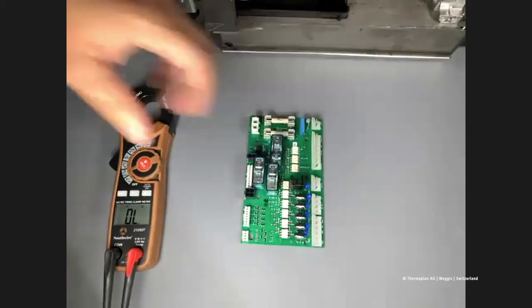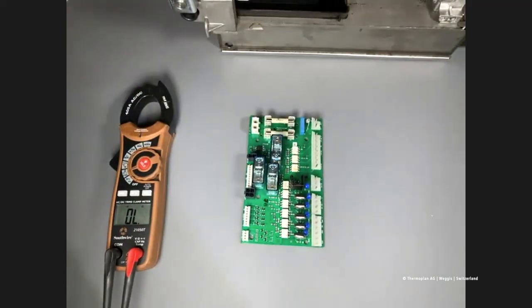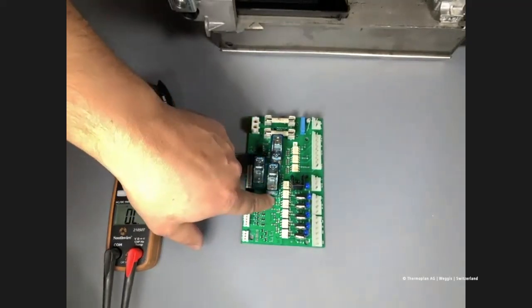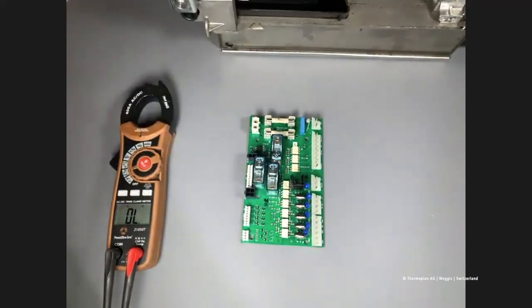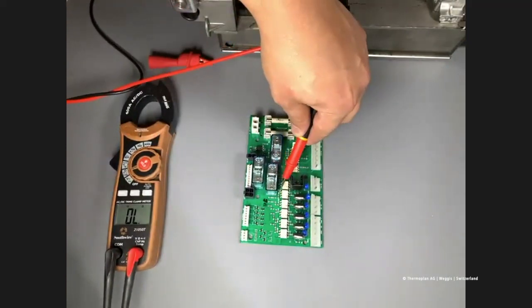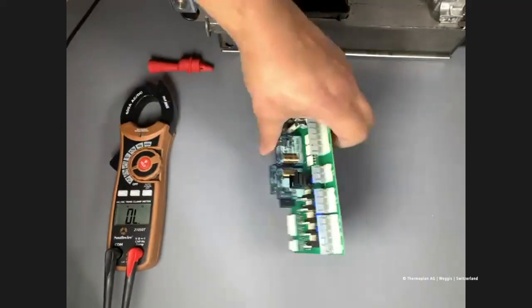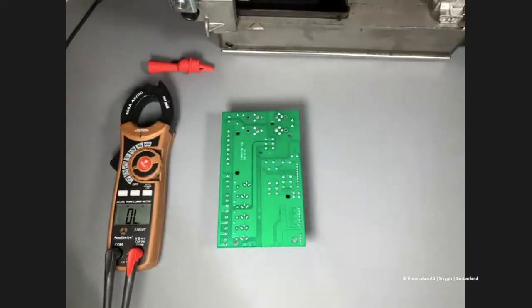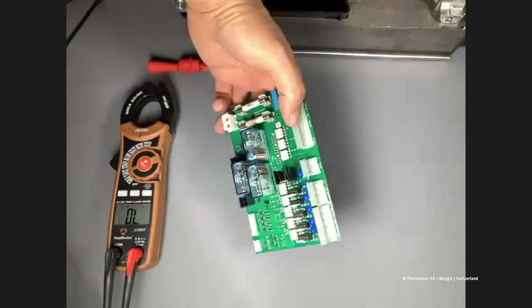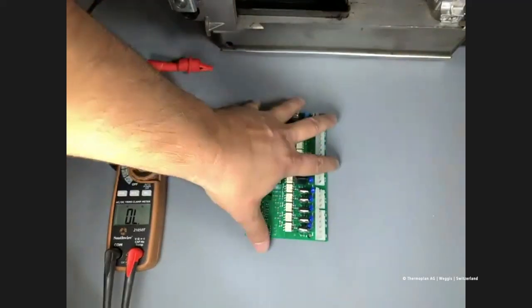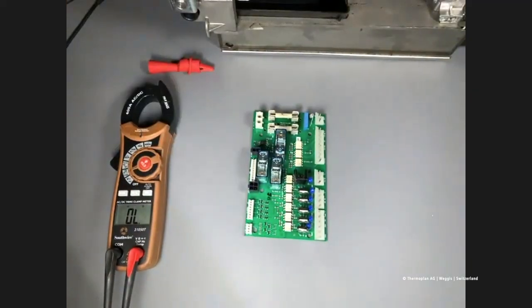So basically, if you're getting the 208 at your pins but the LED here is not illuminated—it's kind of hard to see, but the LED is right here—then you can always test this. If you get tone just like this board, the board is bad. And again, we don't replace anything on the board other than the fuses, so if the board is bad, we just replace the entire board.